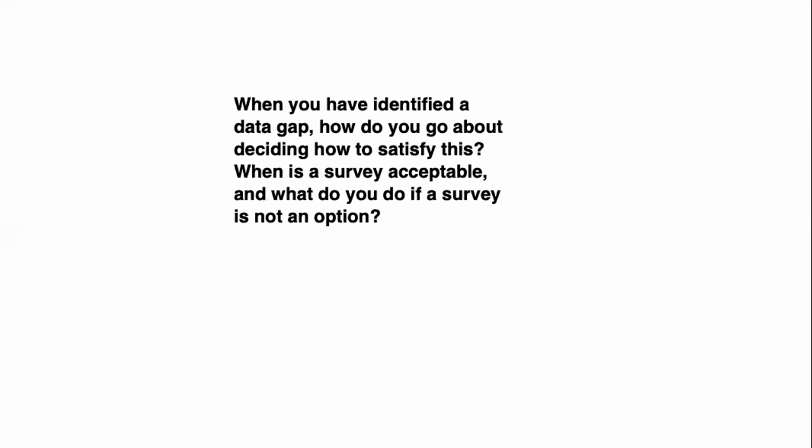Depends on how large the gap is or how you can perhaps mitigate that. How do you go about deciding how to satisfy this? If we're talking about proactive, how do you go about satisfying this in the future, then that does sound certainly like PMCF data. And we certainly have used data from surveys, user surveys, and other such surveys. So how do you go about deciding on how to satisfy this? Well, that would be a part of your PMCF plan.